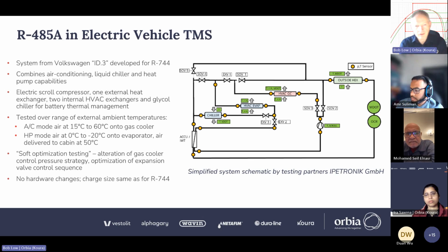It uses a hermetic scroll, so it's the sort of technology you might expect to see in supermarket refrigeration, but it's bolted into a car. And it can run from -20 C ambient air temperature in heat pump mode, all the way up to +60 C ambient temperature onto the gas cooler. So really quite a broad range of application and considerable requirement for flexibility in operation, compared to, say, a simple condensing unit designed for keeping a cold room at a constant temperature.